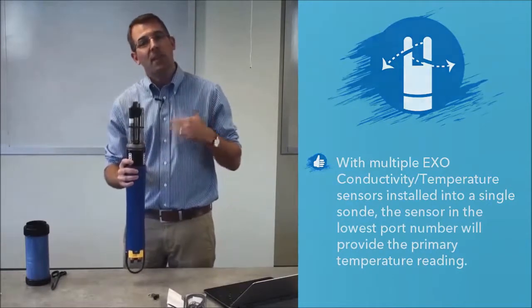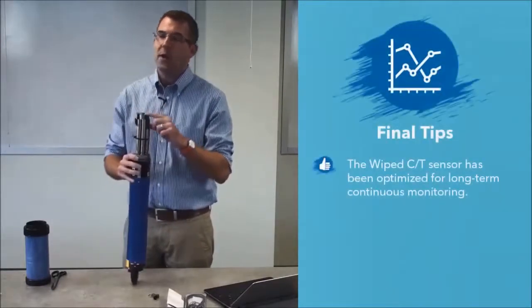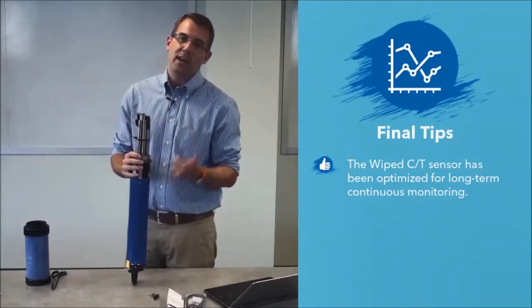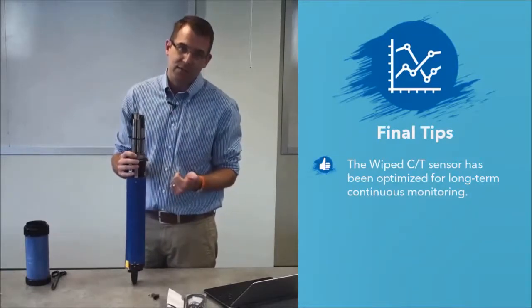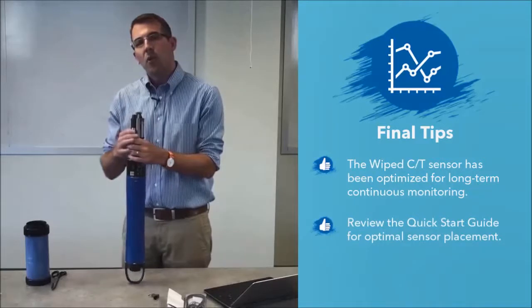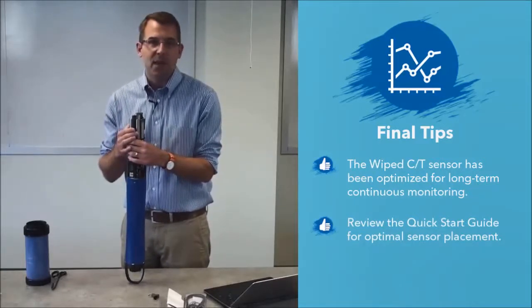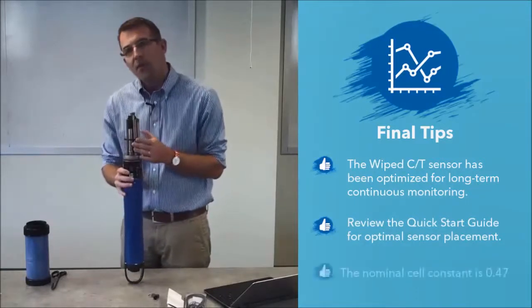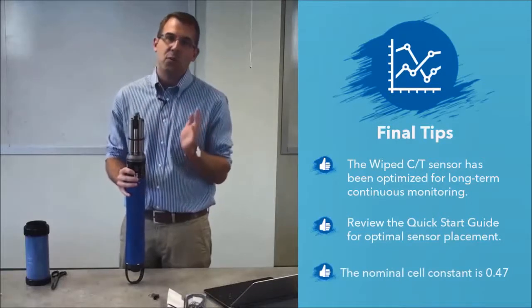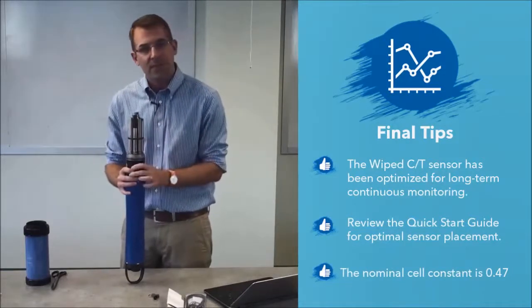And to recap some of the things we talked about before, the Wiped CT is going to perform great in continuous monitoring applications. Keep in mind, port location is important to get the best results, and the nominal cell constant is now going to be 0.47 on Wiped CT.